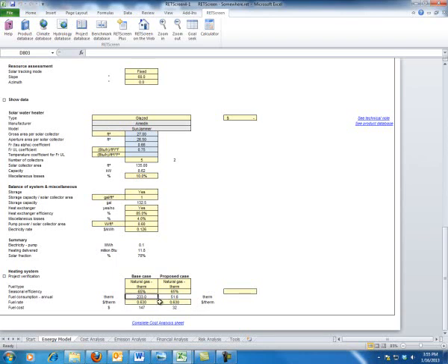But let's just take a quick sneak peek. If I take 223 therms and subtract the 51.6, that gives me 171 therms of net savings. And you're thinking, well, wait a minute. If I had 118 therms of produced heat, but yet you're telling me that I'm saving 171 therms, wait a minute, there's still some waste. And that waste is going up in the 65%.